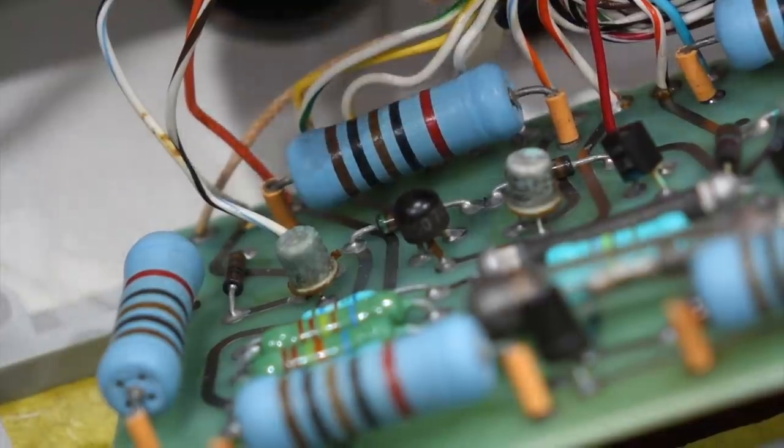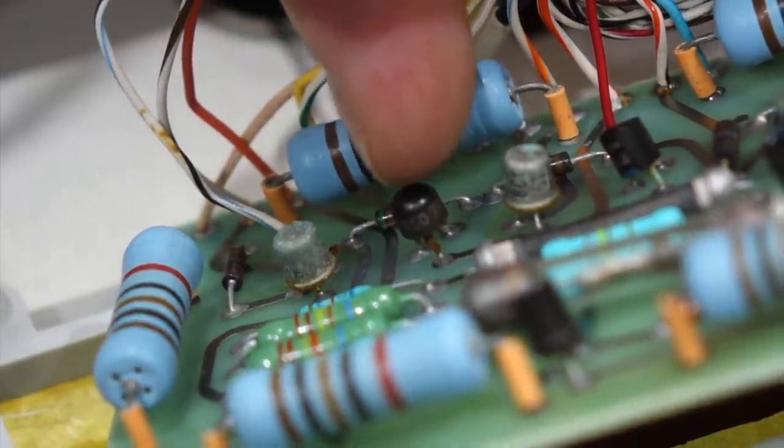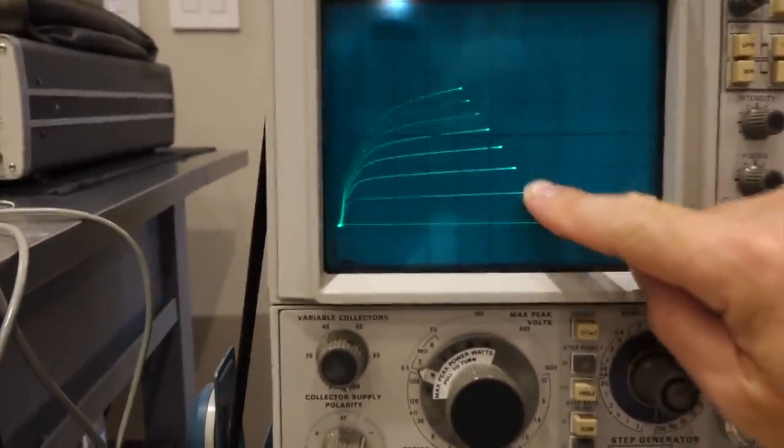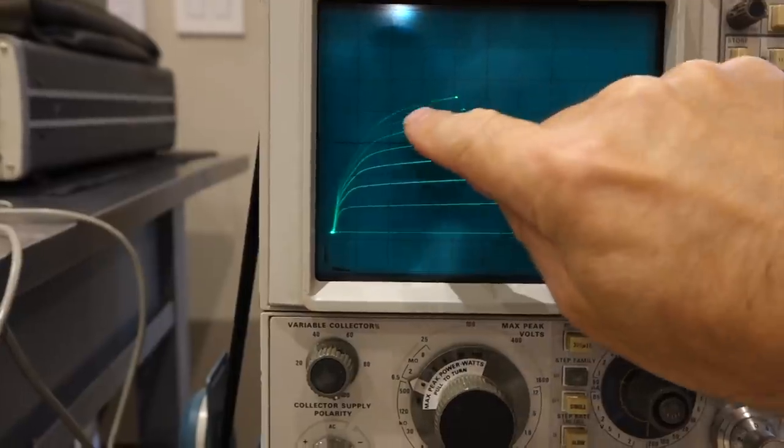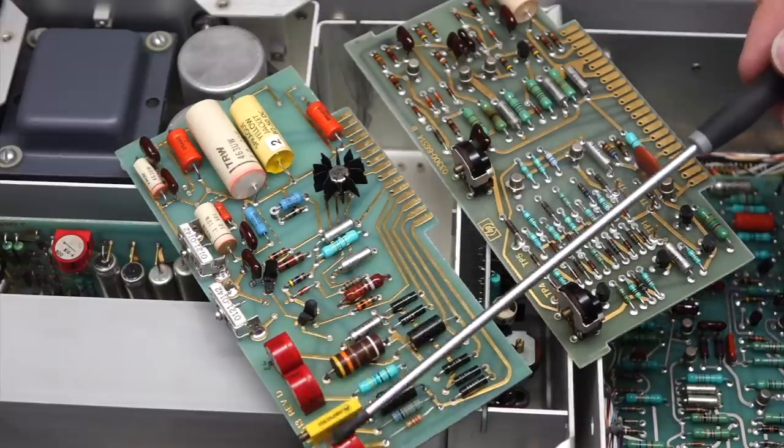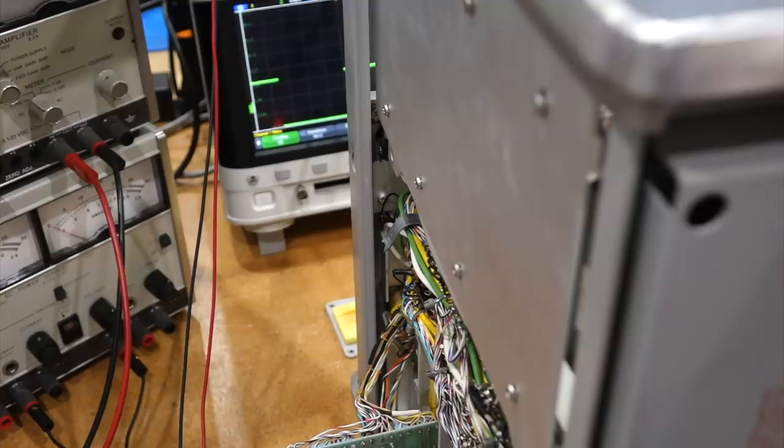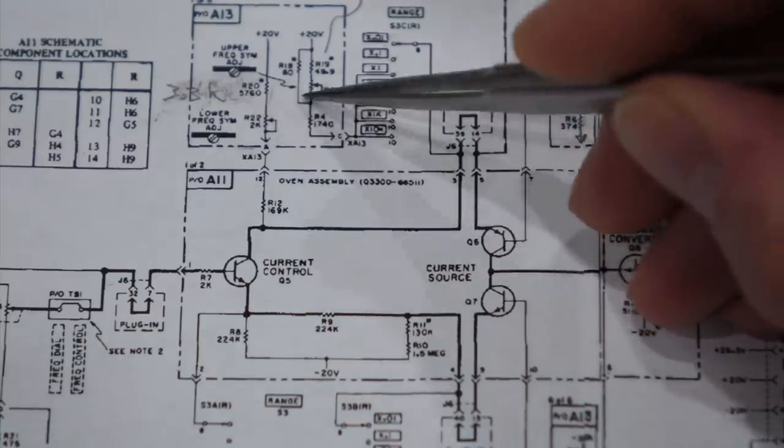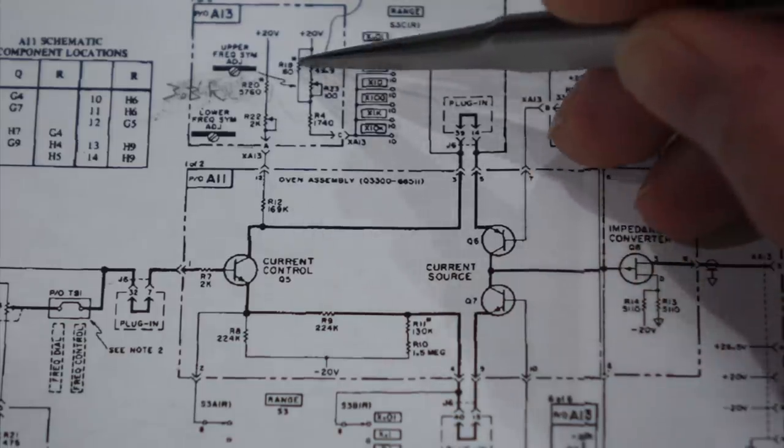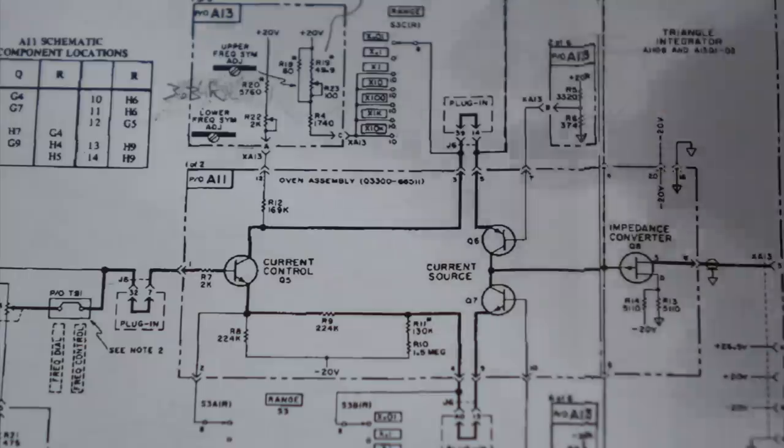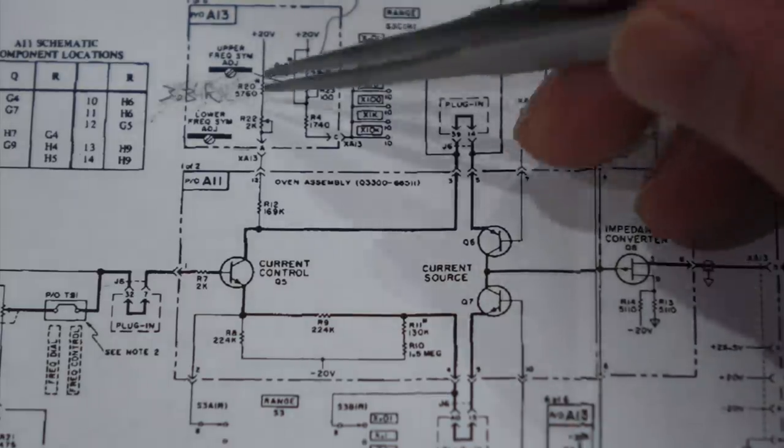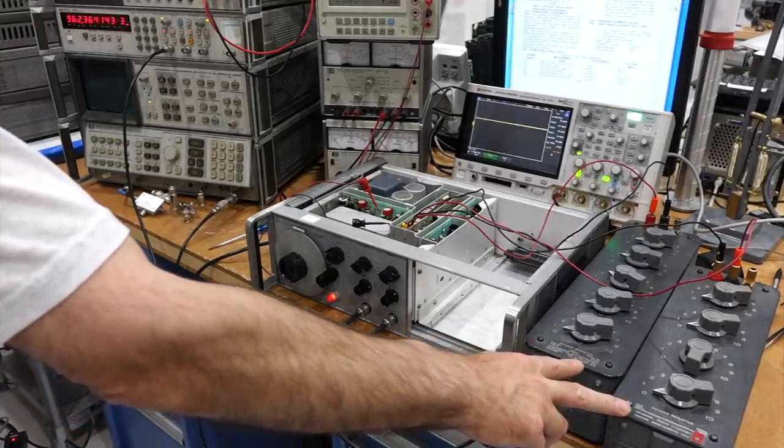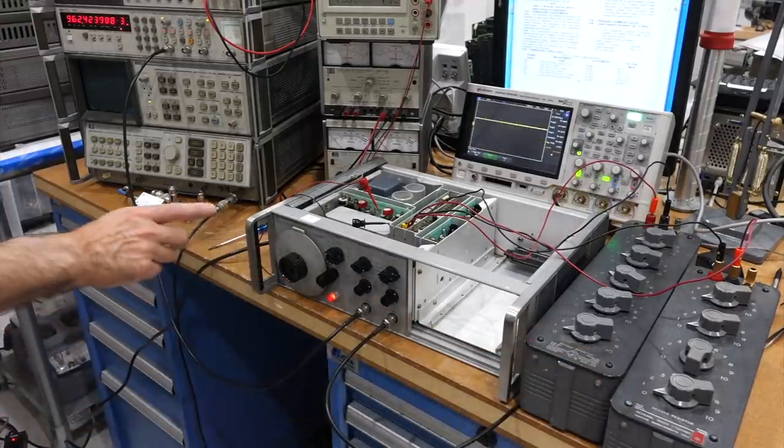Mind you, I still can't get it aligned with the correct procedure, but at least it is much closer. So would I have been able to bring it back to spec with the original transistor still in? I actually don't know. I believe the rusty transistor was drifting and about to die, causing the symmetry problem in the first place. But this mishap was a blessing in disguise. It forced me to scrutinize the unit very closely, root out the rusted transistor before failure, and cure the supply instability. So I think all I have to do now is indeed readjust the resistors. I'll end up with a resistor that's close to what was chosen on the factory. I changed the transistor, so I expect that this resistor has to change anyhow. I have to redo the resistors from the factory selected resistors. But now it works.